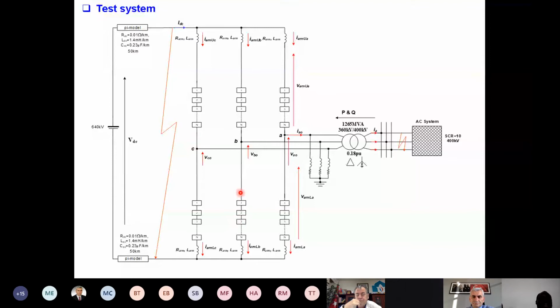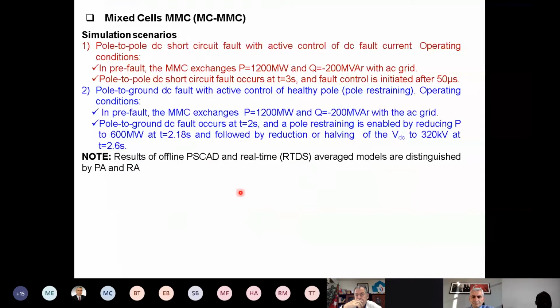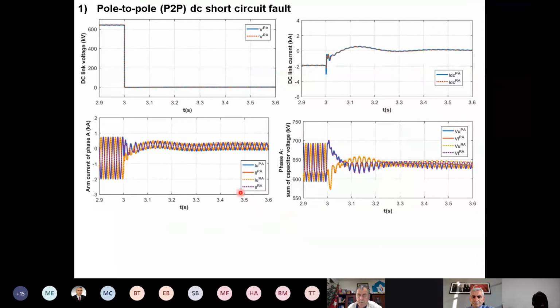And we added fault control here. In this, you can see the DC voltage drops to 0, but the DC current is controlled to 0 quickly. And importantly, you can see the arm current also remains well controlled. And I'll show you why you have some current in the arm current. And here, these are the arm capacitor voltages. You can see everything is under control.